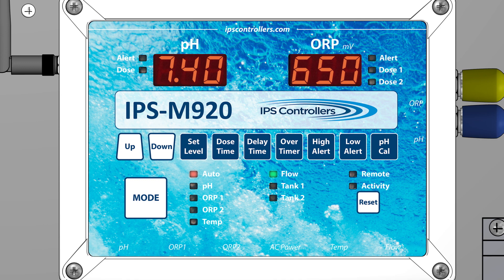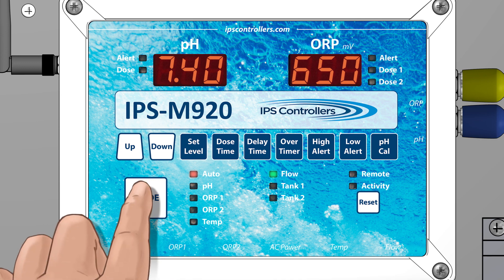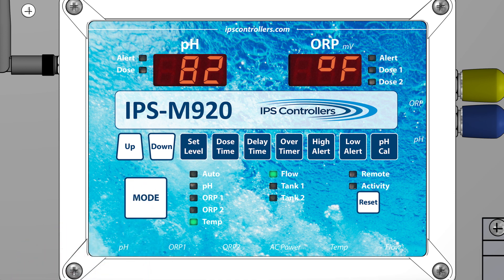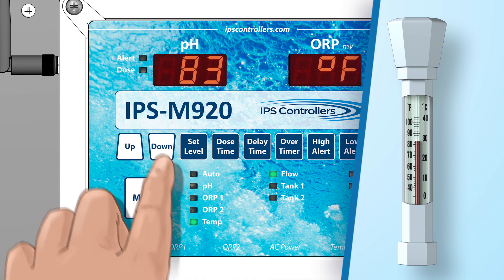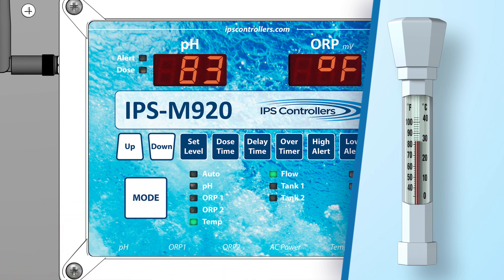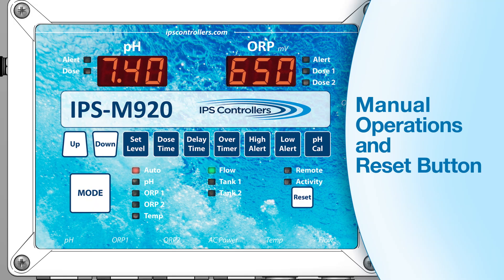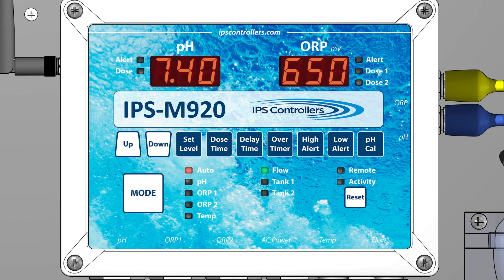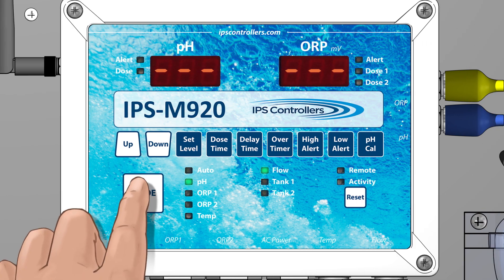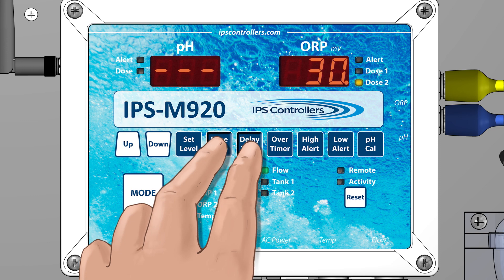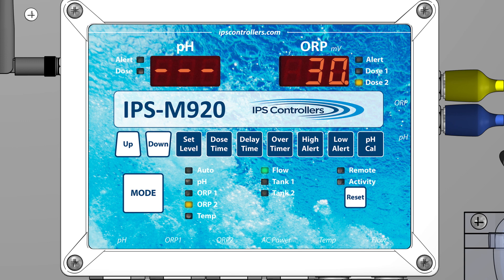If the temperature sensor is installed, the water temperature will be displayed in the digital display window. Press and release the Mode button and cycle through to the Temp mode. Using the Up or Down buttons, the temperature can be calibrated up or down by 10 degrees. The reading can be changed from Fahrenheit to Celsius by pressing the pH Cal button. You can manually force the controller to run a dose cycle in the pH, ORP1, and ORP2 modes if the mode is in a timed feed setting. Hold down the Dose Time button and then press the Delay Time button; the controller will dose for the time set in the dose time setting.